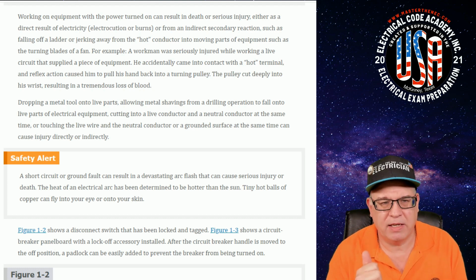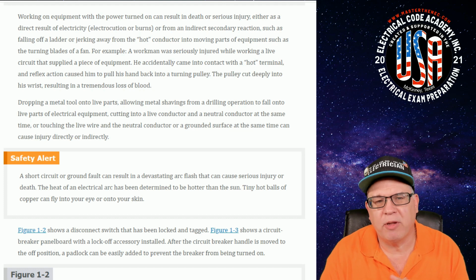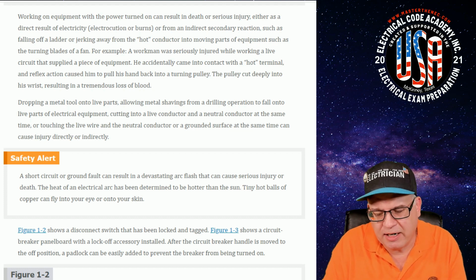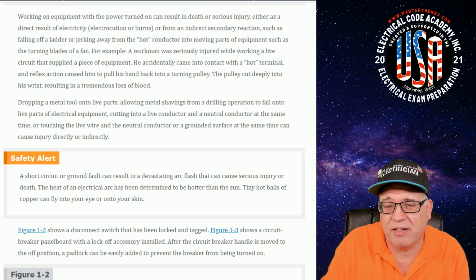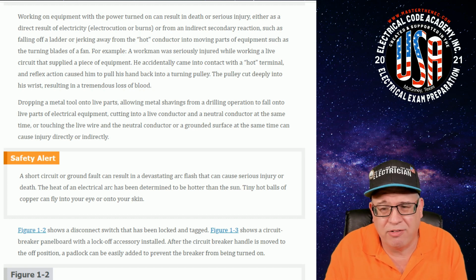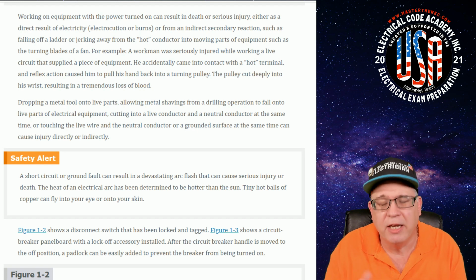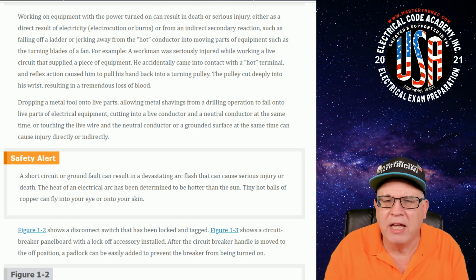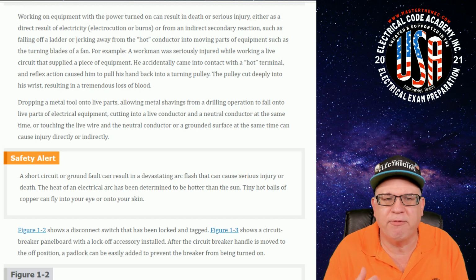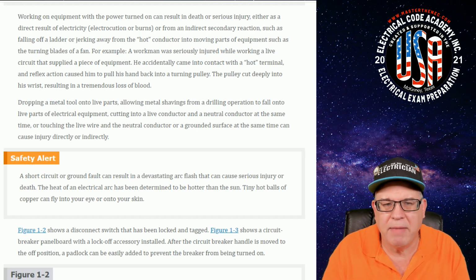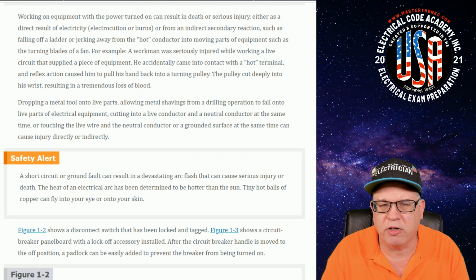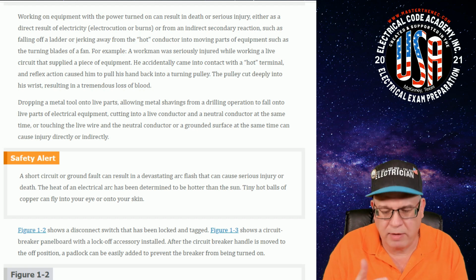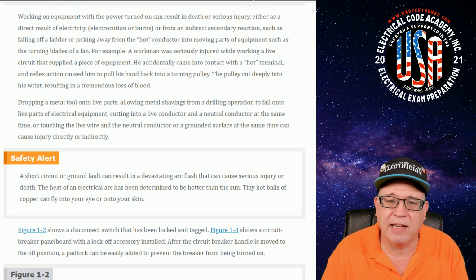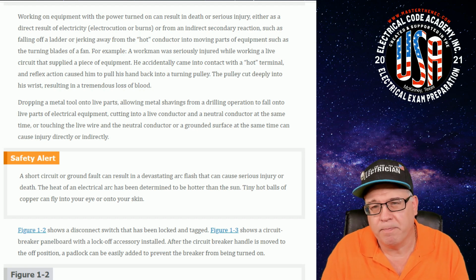Next thing - what if you're working on something and trying to work around it very cautiously, but you don't want to de-energize it, either because you're lazy or you just don't want to go to the panel and hunt for it? You're using a tool or drilling into a box, and you have the metal shavings, the filings, fall into the live parts. Maybe they cut into a live conductor and a neutral conductor at the same time, creating a dead short. Or maybe they fall onto an ungrounded hot conductor and it comes in contact with a grounded surface at the same time - then it creates an arc flash.